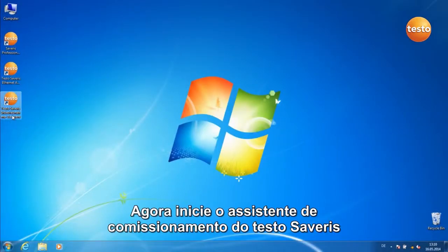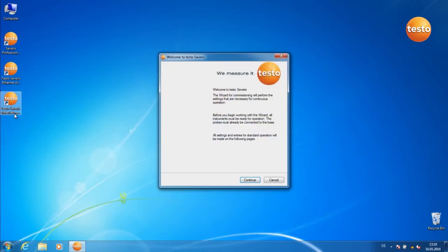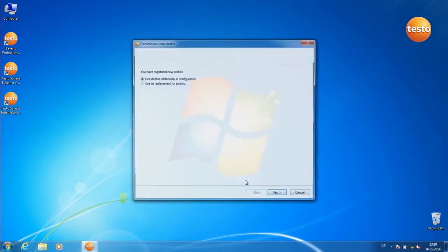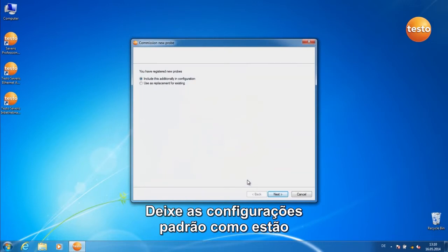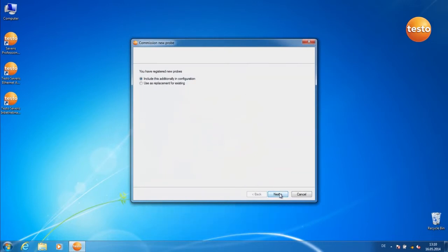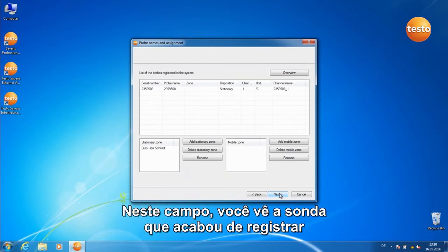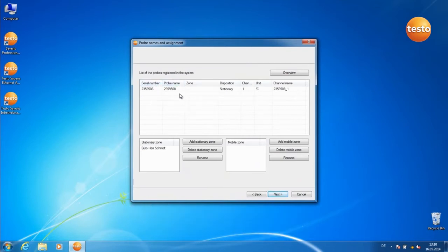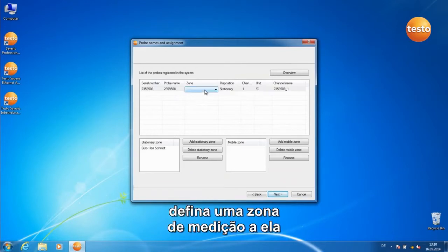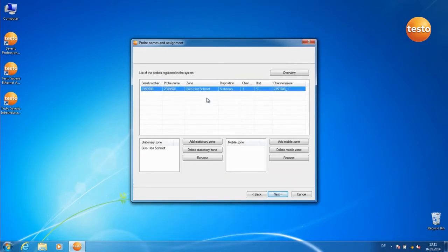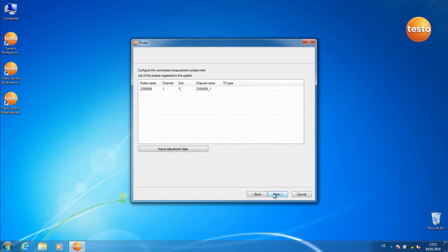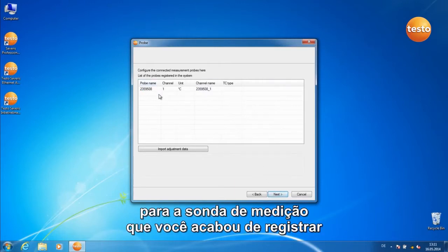Now start the Testo Saveris Commissioning Assistant. Leave the standard settings as they are. In this dialog, you see the probe you've just registered. Allocate a measurement zone to it. Here you can make more configurations to the measurement probe you've just registered.